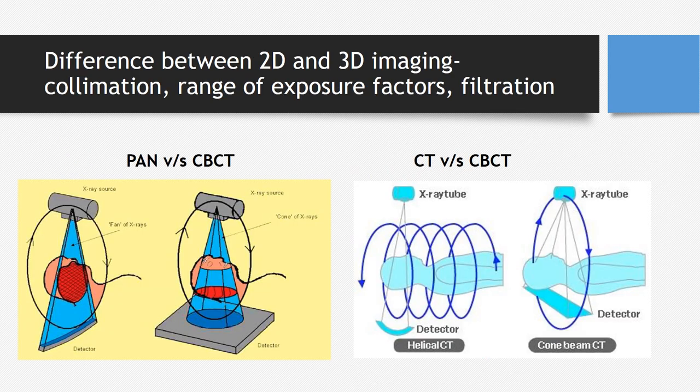The difference between two-dimensional and three-dimensional imaging — comparing panoramic versus CBCT — is that the panoramic uses a slit beam or fan beam of x-rays, which exposes one particular area in the focal trough, giving a two-dimensional image. Versus cone beam computed tomography, which uses volumetric imaging with a cone of x-rays, helping you visualize all objects within that conical area of exposure. It is best suited for the head and neck region because of its ease, convenience, and availability.